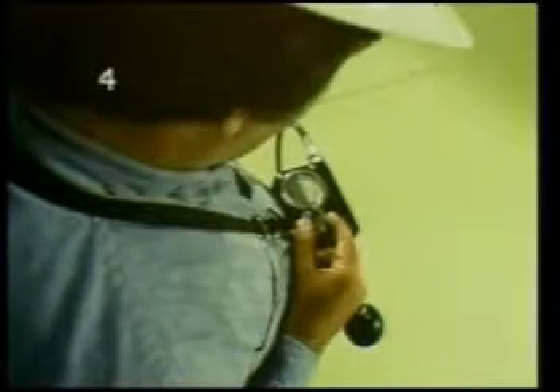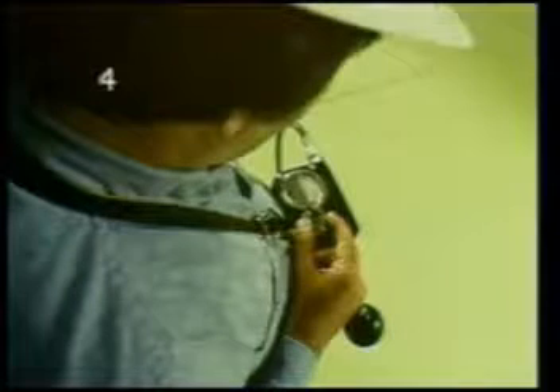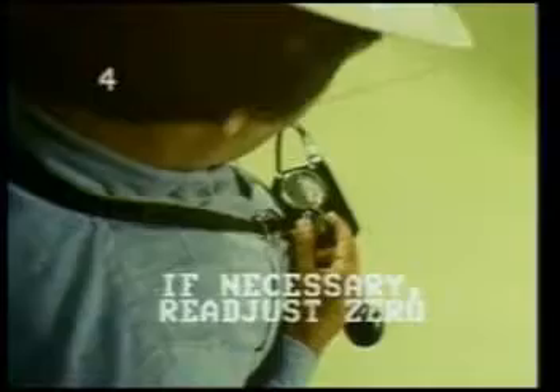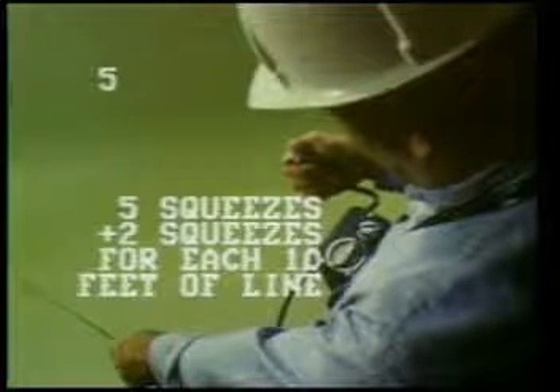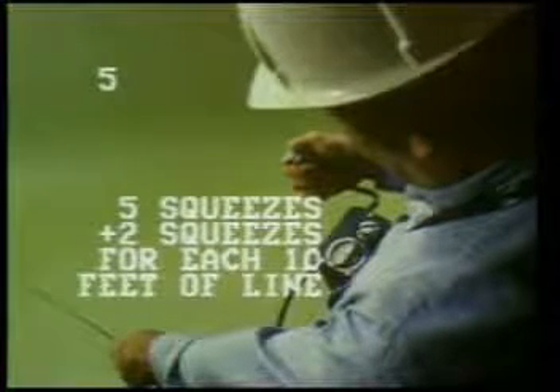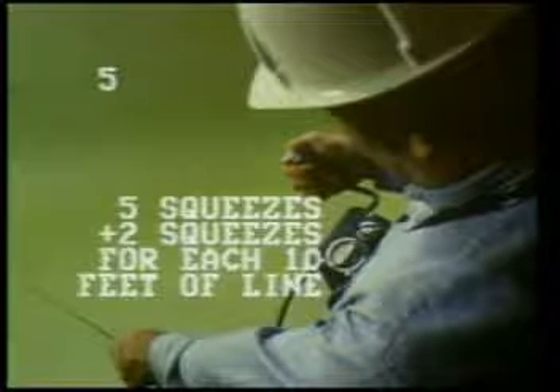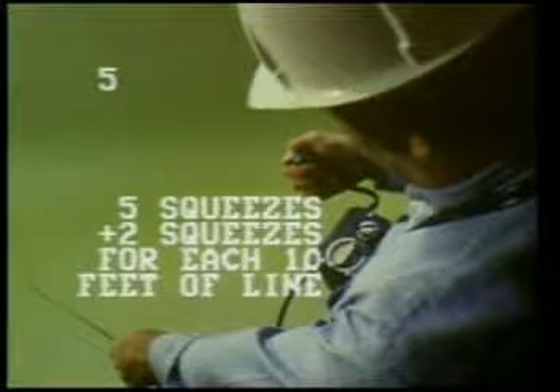4. Get the instrument and sampling line in position, and if necessary, readjust the meter pointer to 0 before sampling. 5. Now you're ready to sample. 5 squeezes of the bulb, plus 2 squeezes for each 10 feet of sampling line, should be enough to draw the sample through the instrument, but keep squeezing until you get the highest reading.